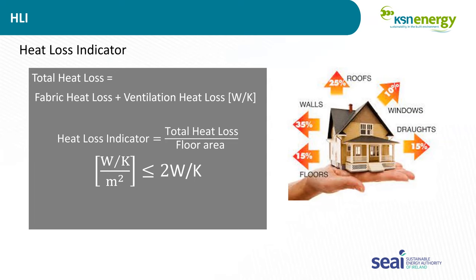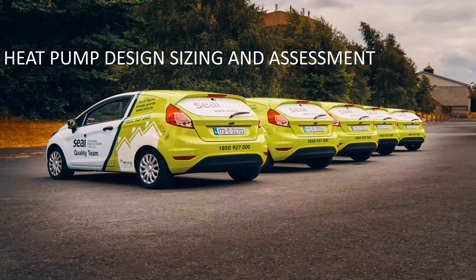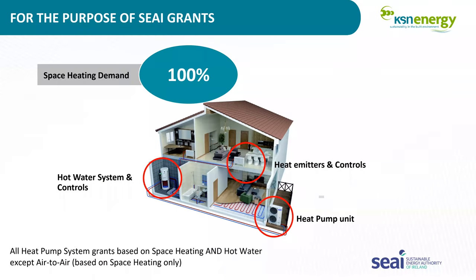After the home has been deemed fit for having a heat pump installed, the next step is the design, size and assessment, which needs to come into consideration. For the purpose of SEAI grants, the first thing is the heat pump has to be able to deliver 100% of the space heating needs. That means you can't say it'll heat the house but we have to put the fire on as well, or we need a backup boiler or anything like that.